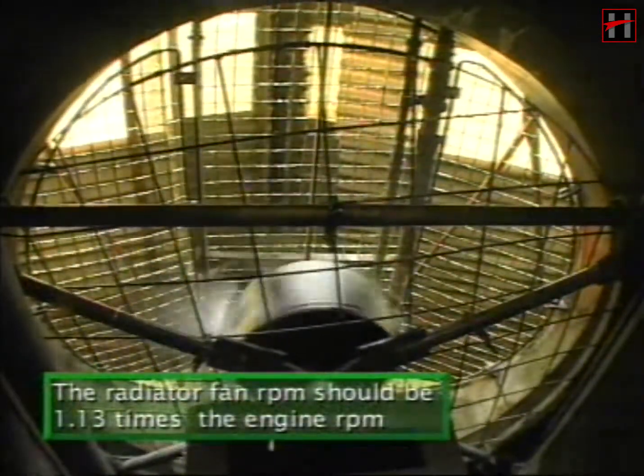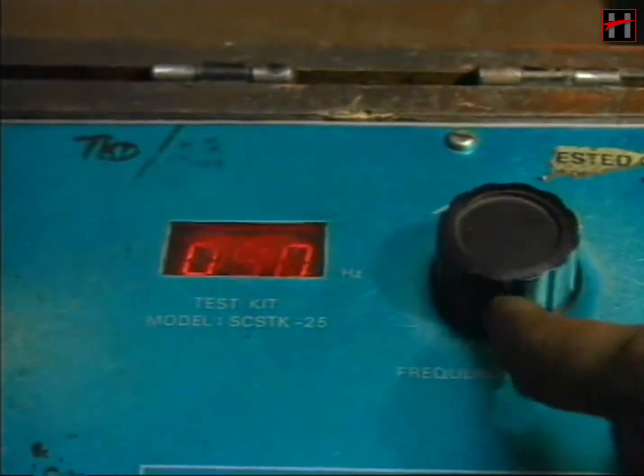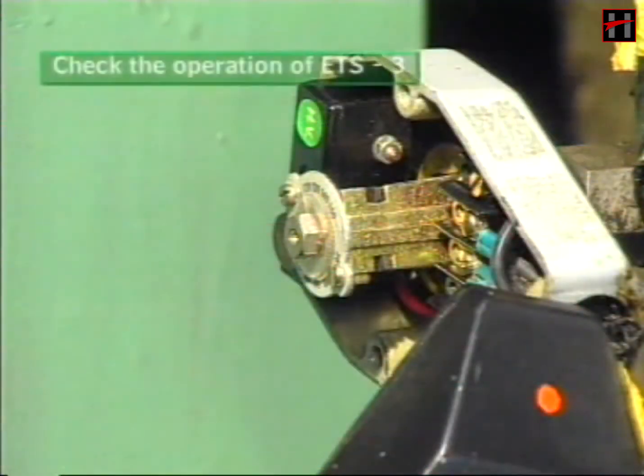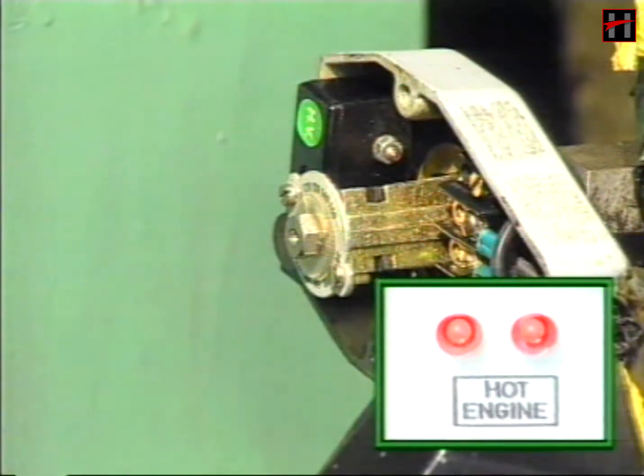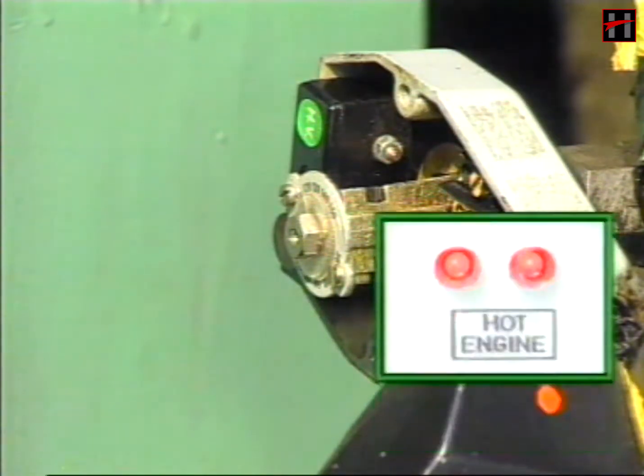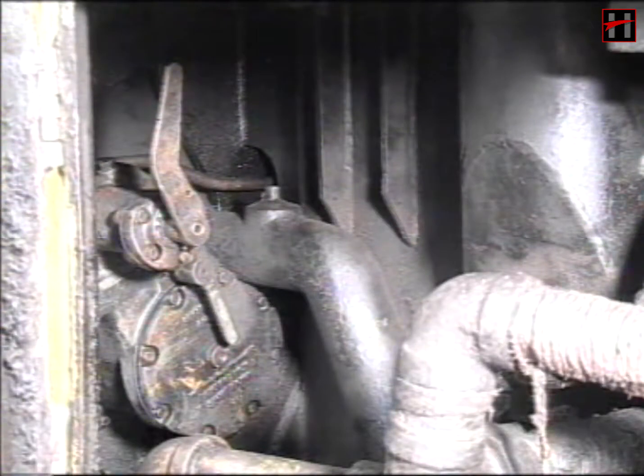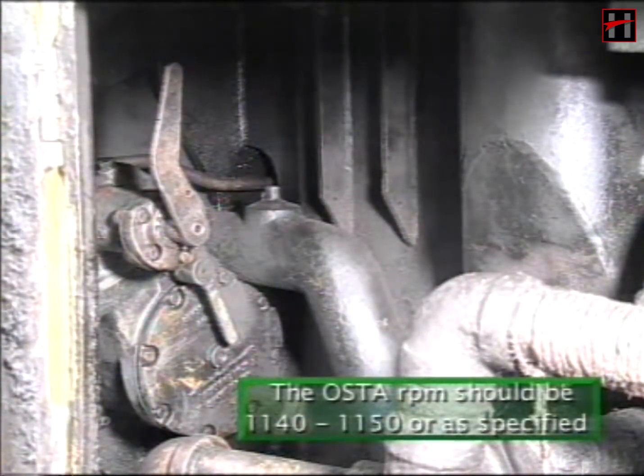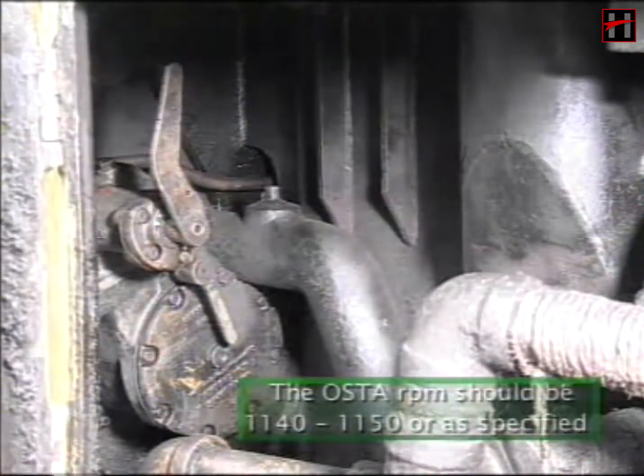In the C schedule of incoming examination, measure the radiator fan RPM with a stroboscope. The radiator fan RPM should be 1.13 times the engine RPM. Check the transition settings as required. Check the operation of engine temperature switch 3. The hot engine alarm and indication should come at 90 degrees centigrade. Check the overspeed trip assembly RPM. By using a multimeter, the OSTA RPM should be 1140 to 1150 or as specified.